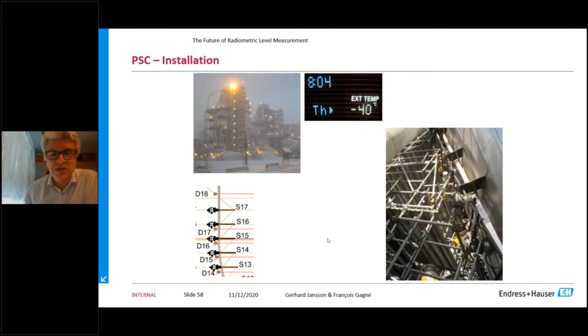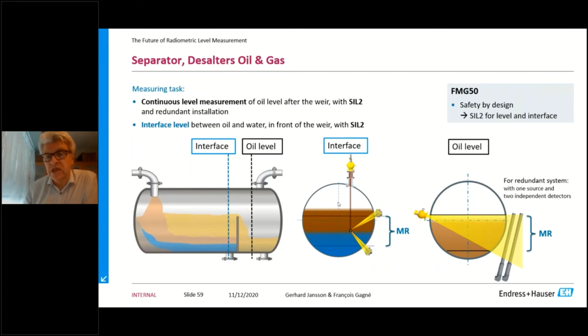Otherwise, in oil and gas, very often what we try to do is the interface between the oil, emulsion layers, and water, and there are different ways of doing this. Very often we'll have an isotope installed through a dry well into a certain position in the vessel, with detectors on the outside. We can of course go across, but that means a much higher source activity, so we try to use internal sources instead.